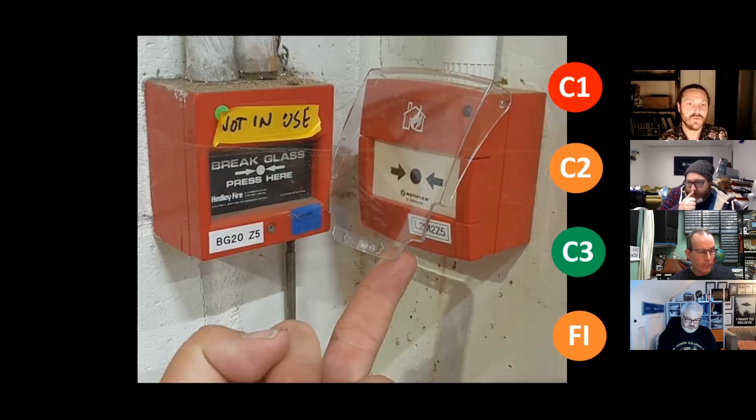So for years, we've installed FP or fire rated cabling, whatever you want to install. And we don't just put clips every 1 meter. We install them to manufacturer's instructions and we install them to make sure that the fire integrity is maintained, i.e., we want to keep those cables clipped to the building fabric so it stays there and does its job. So if a fire occurs and cables start expanding, things start moving within the building, we want to keep the cable still. We don't want them to start pulling out under mechanical stress, and also things like maintenance. The amount of times that I've had cables pulled out where someone's got their hand above the ceiling trying to pull some new alarm cables and whatever, and they've damaged the fire alarm system.